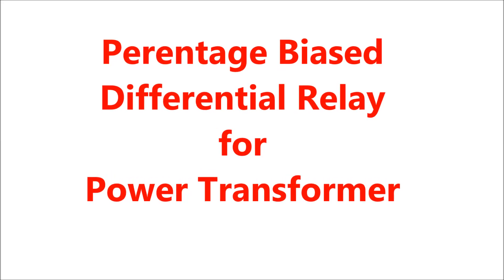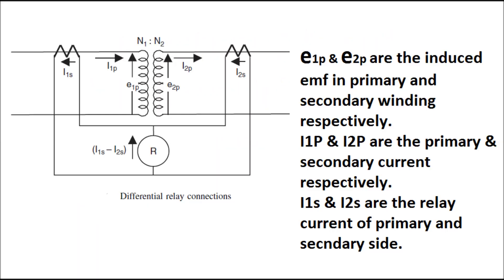Percentage Biased Differential Relay for Power Transformers. To understand the principle of differential relay, an example is taken for a single-phase power transformer. Here N1 is the turn ratio of the transformer. E1p and E2p are the induced EMF in the primary and secondary winding respectively. I1p and I2p are the primary and secondary current respectively. I1s and I2s are the relay currents of the primary and secondary side of the power transformer.